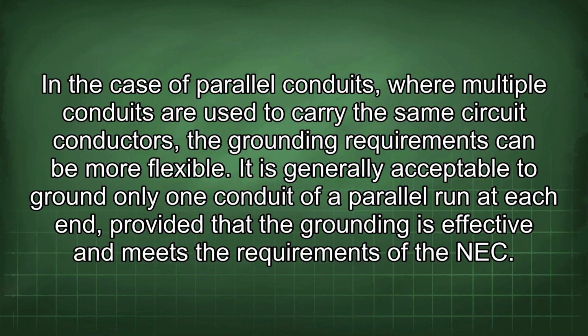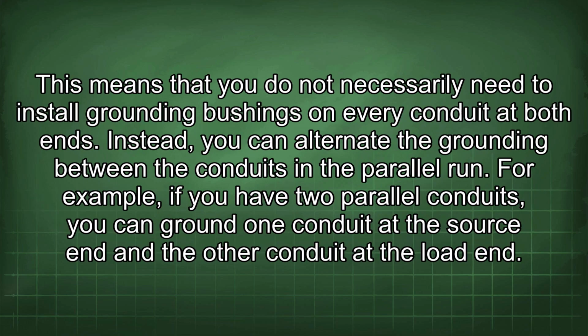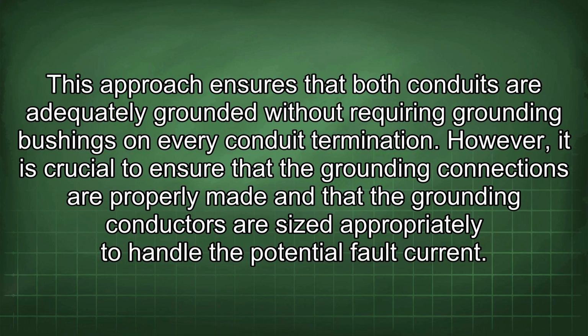It is generally acceptable to ground only one conduit of a parallel run at each end, provided that the grounding is effective and meets the requirements of the NEC. This means that you do not necessarily need to install grounding bushings on every conduit at both ends. Instead, you can alternate the grounding between the conduits in the parallel run. For example, if you have two parallel conduits, you can ground one conduit at the source end and the other conduit at the load end. This approach ensures that both conduits are adequately grounded without requiring grounding bushings on every conduit termination.